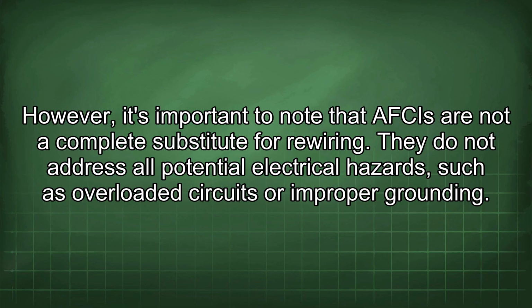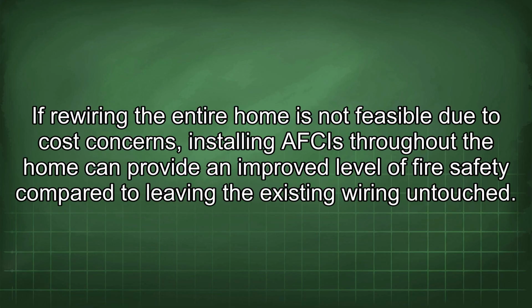However, it's important to note that AFCIs are not a complete substitute for rewiring. They do not address all potential electrical hazards, such as overloaded circuits or improper grounding. If rewiring the entire home is not feasible due to cost concerns, installing AFCIs throughout the home can provide an improved level of fire safety compared to leaving the existing wiring untouched.